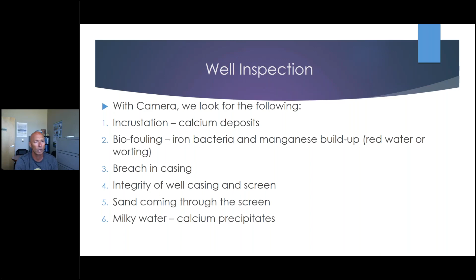Biofouling is also caused by iron bacteria, H2S sulfur-reducing bacteria, and manganese. Iron bacteria forms a jelly-like slime. Biofouling occurs when enough biofilm accumulates to reduce water flow. In this picture, just below the hand, you can see the screen is almost completely plugged off, and the only way to remove that inside the well is through acid treatment.